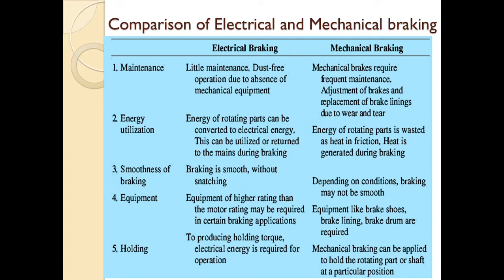For maintenance, electrical braking requires little maintenance because of dust-free operation due to the absence of mechanical equipment. But in mechanical braking, mechanical brakes require frequent maintenance, adjustment of brakes, and replacement of brake linings due to wear and tear. For energy utilization in electrical braking, energy of rotating parts can be converted to electrical energy, which can be utilized or returned to the mains during braking. Whereas in mechanical braking, energy of rotating parts is wasted as heat in friction.